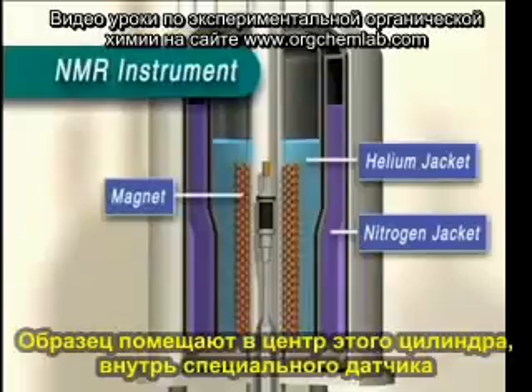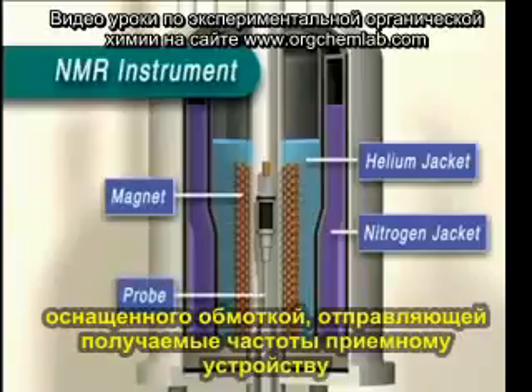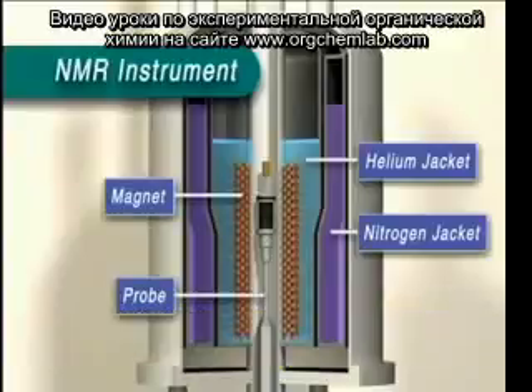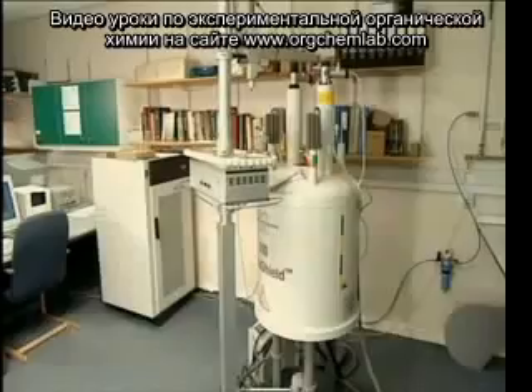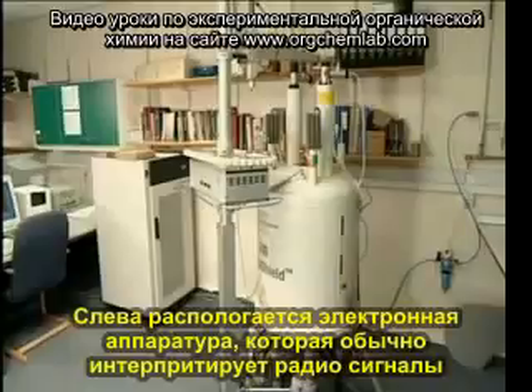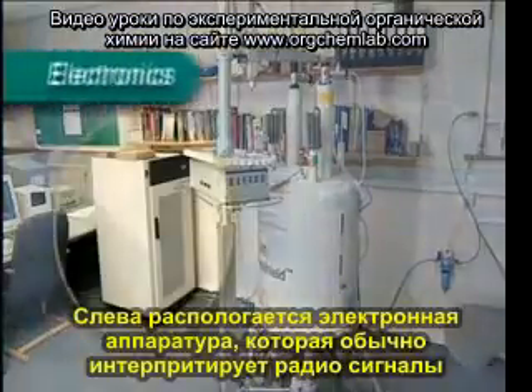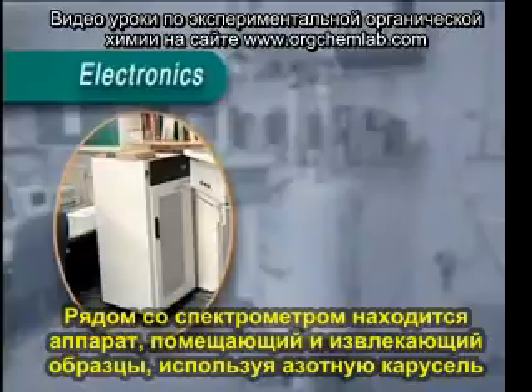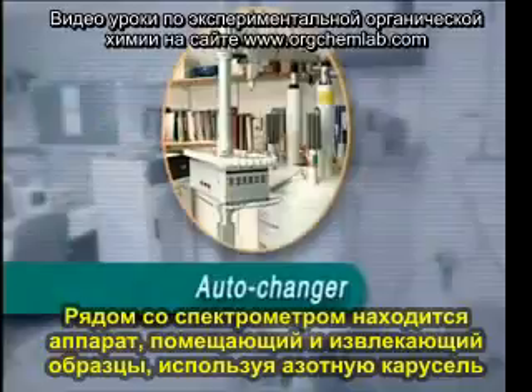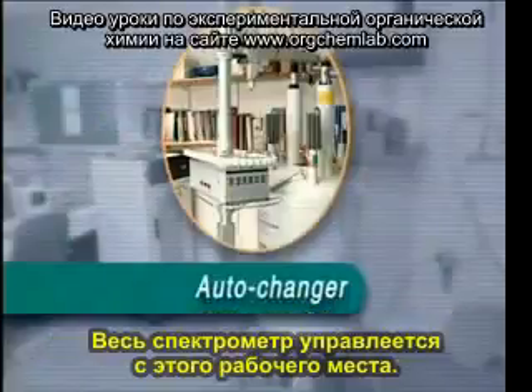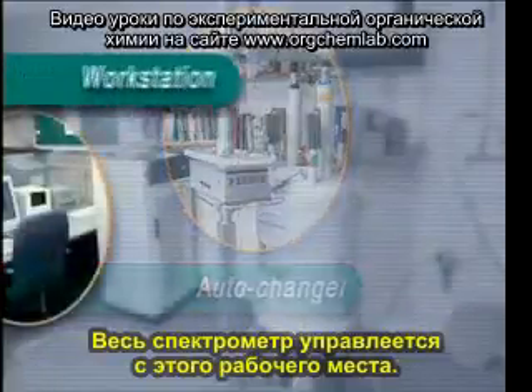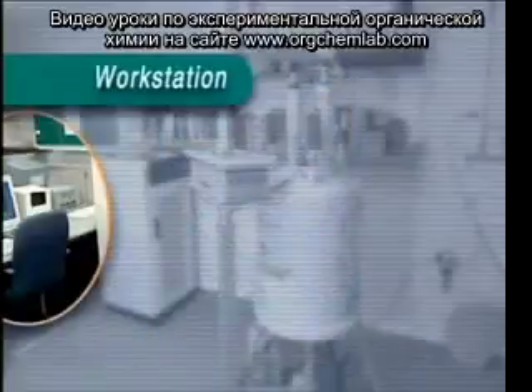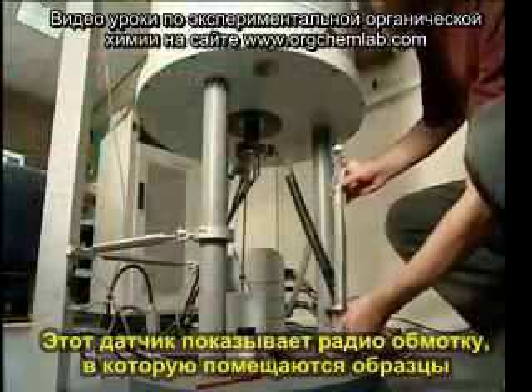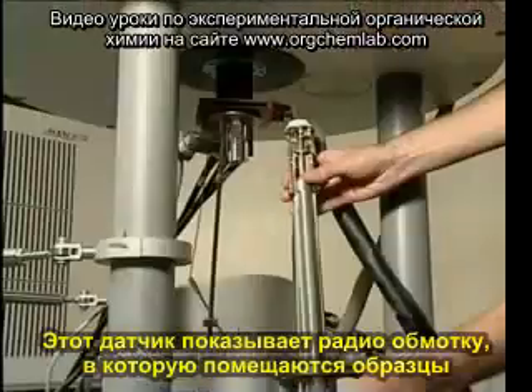The sample sits in the centre of the cylinder inside this probe, which contains the coils that send and receive the radio frequency signals. The electronics which generate and interpret the radio signals are housed in the boxes to the left. Samples are placed in the machine and removed from it by the auto changer, which takes the samples in turn from the carousel. The instrument is controlled from this workstation. This spare probe shows the radio coils and where the sample sits.